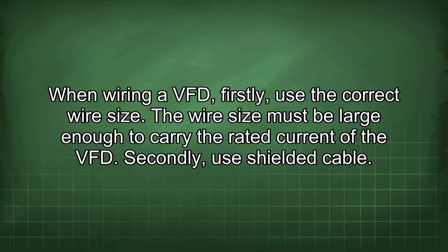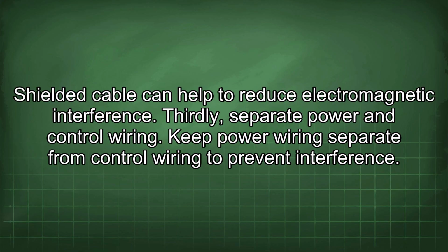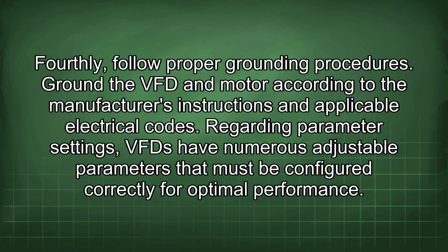When wiring a VFD, firstly, use the correct wire size. The wire size must be large enough to carry the rated current of the VFD. Secondly, use shielded cable. Shielded cable can help to reduce electromagnetic interference. Thirdly, separate power and control wiring. Keep power wiring separate from control wiring to prevent interference. Fourthly, follow proper grounding procedures. Ground the VFD and motor according to the manufacturer's instructions and applicable electrical codes.